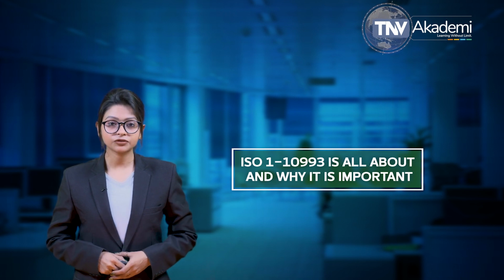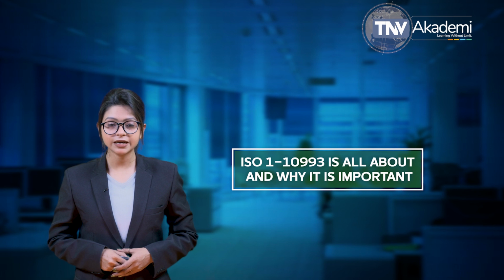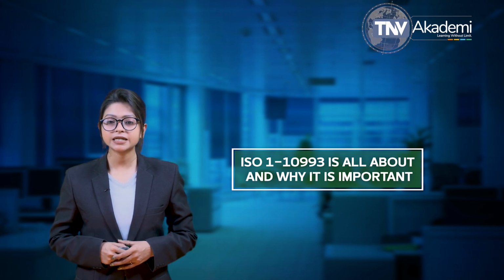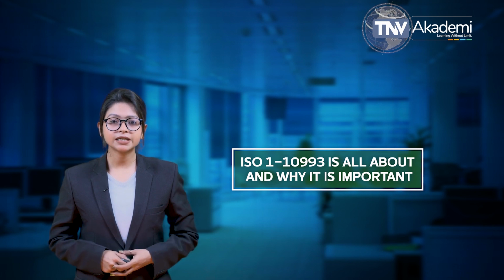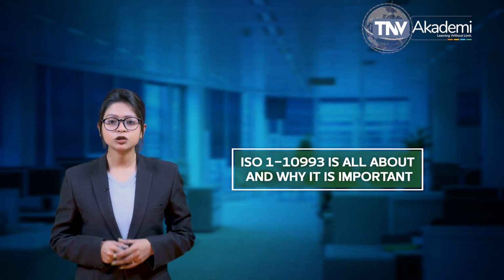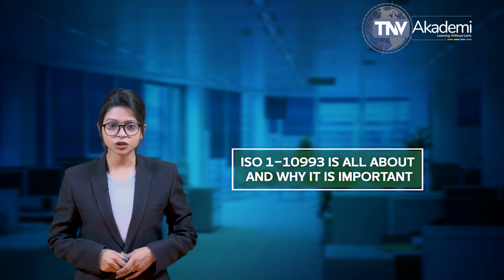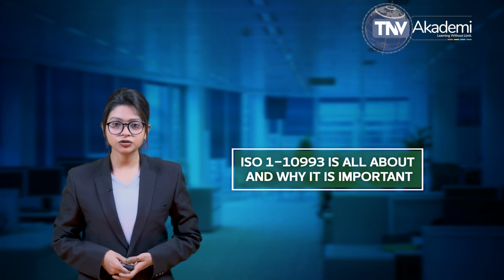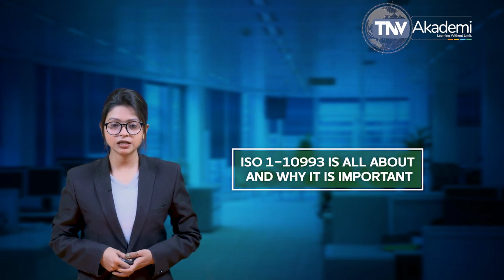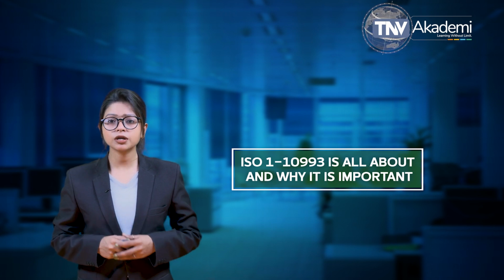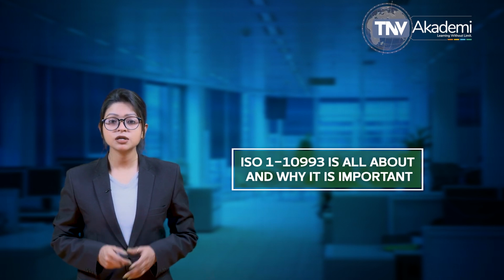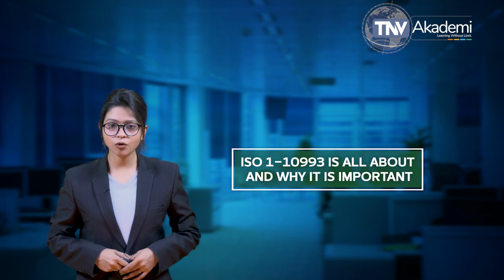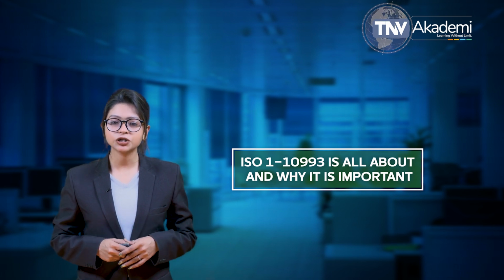ISO 10993-1 is the first part of a series of standards to evaluate the biocompatibility of medical devices. Biocompatibility, as defined by the FDA, is the ability of a device material to perform with an appropriate host response in a specific situation. In other words, manufacturers need to ensure that the various materials and manufacturing processes used in a device or a device delivery system support safety or do not pose risk to patients or clinicians.